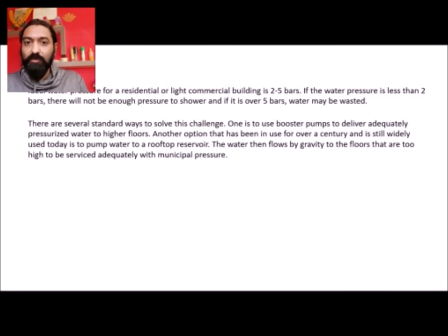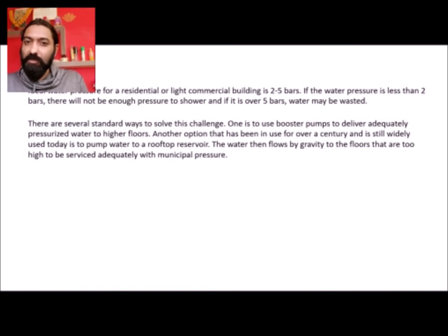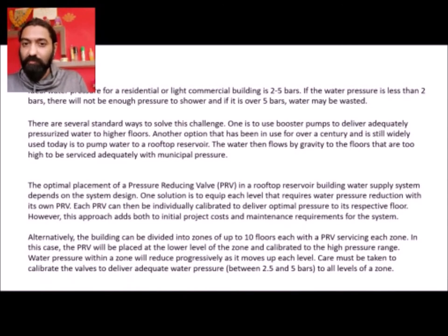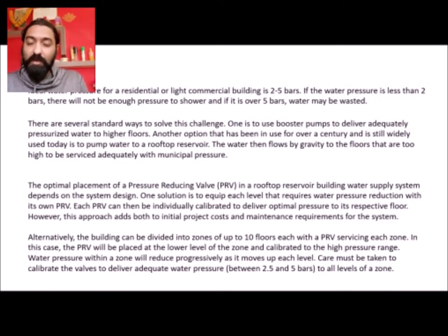The ideal pressure for residential or light commercial buildings is two to five bars. A bar is a unit of measurement of water pressure. If water pressure is less than two bars, it is not enough to pressurize a shower. If it is more than five bars, you are wasting a lot of water. So as an architect, the main concern is to maintain water pressure between two to five bars.